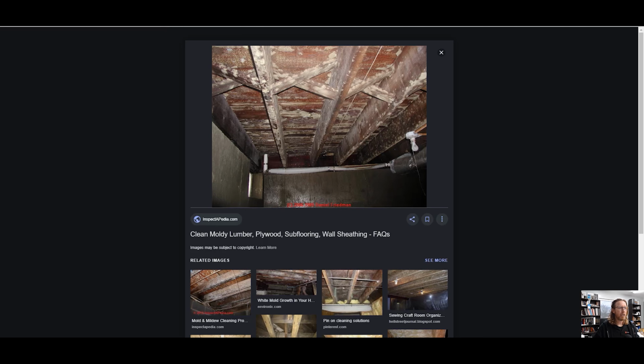So the first thing I want to look at is, are you controlling humidity? Because if you don't control humidity, you start to get condensation from your ductwork, as you can see right here, we've got ductwork that is inside the crawl space. Obviously, this is a tongue and groove system. It may or may not have as wide gaps as what you have, but it sounds like you've got a subfloor and a carpet directly on top of that. Most homes will have a subfloor and then another flooring on top, and then either the finished carpet or the hardwood or whatever. So if you've got a tongue and groove that's got some major gaps, and the only thing between those gaps and the crawl space is your carpeting, then you're going to have a lot of drafting.